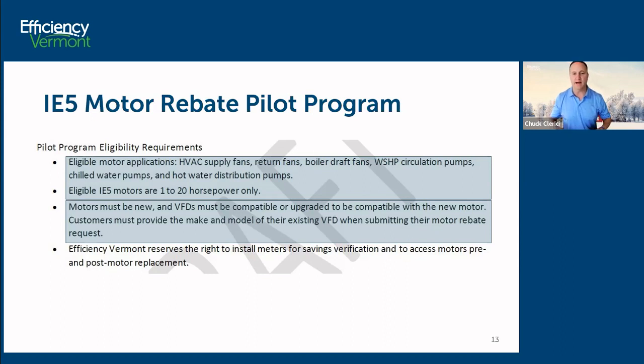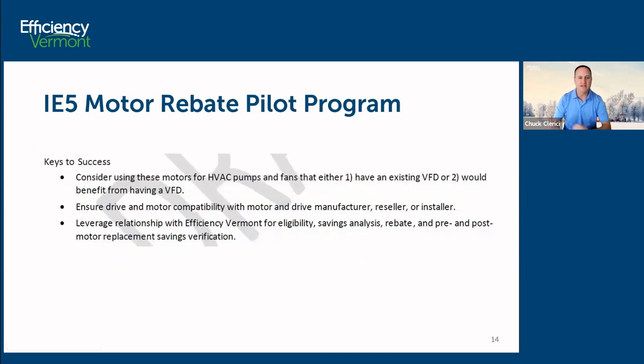Customers must provide the make and model of their existing VFD when submitting their motor rebate. This is to make sure that we take the verification step to make sure the new IE5 motor will work with any existing VFDs. And as with most of our projects, Efficiency Vermont reserves a right to install meters for savings verification and to access motors pre and post replacement. That's a big piece of this pilot program. We are learning. We've learned a lot about these IE5 motors, but we still have more to learn, particularly around the part load efficiency.